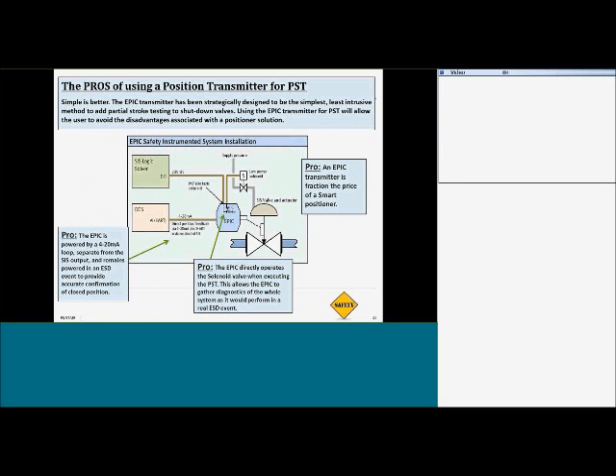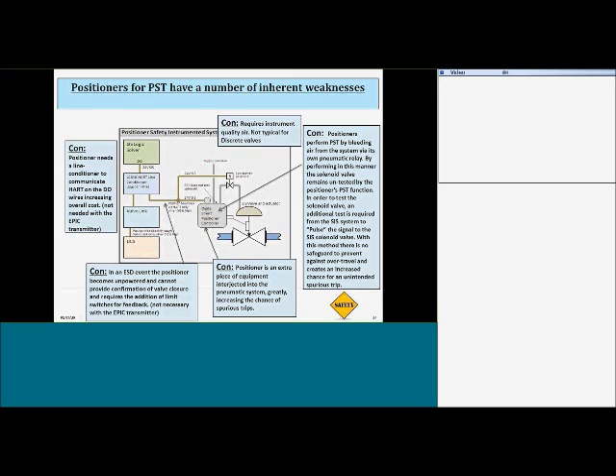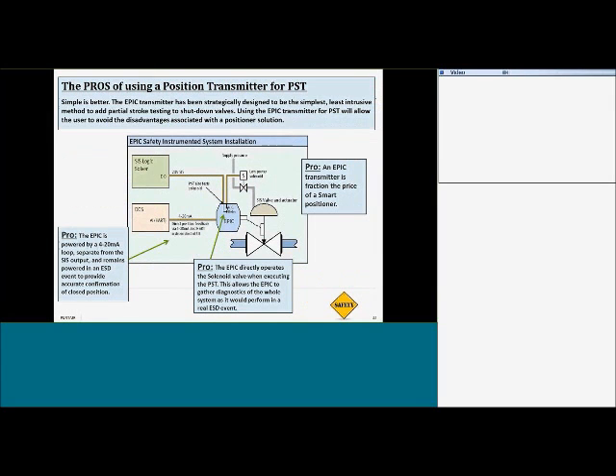Unfortunately, a lot of the devices that have been out there for partial stroke testing, like positioners, have a lot of inherent issues when it comes to partial stroke testing. They're very, very complex designs for systems with positioners so that they can do partial stroke testing. For example, the positioner does not utilize the solenoid valve for the partial stroke test. So some customers have thrown this completely out and said we won't do partial stroke testing unless we add in another position transmitter and some other components and design a very complex system that does more than just pulse the solenoid valve. So we get pretty deep here, and this is part of the Westlock Epic presentation.